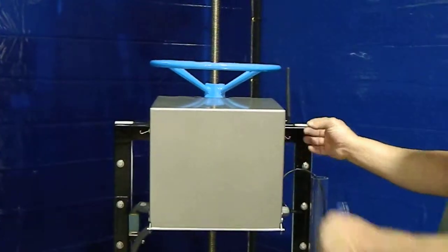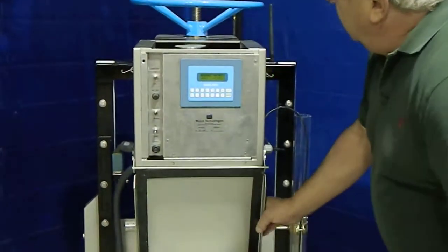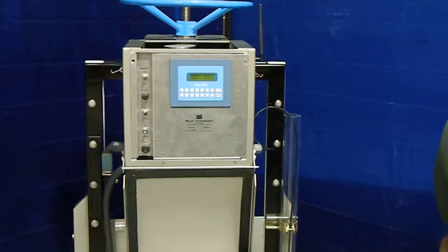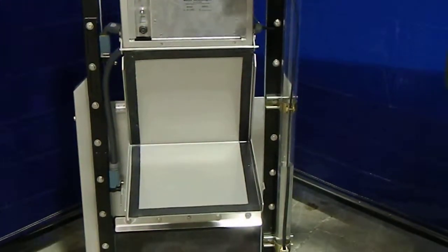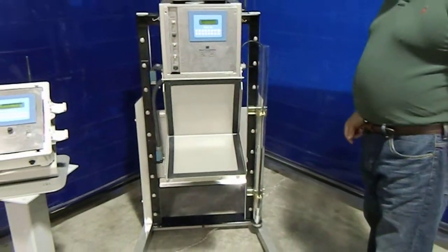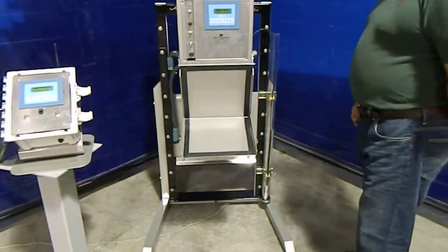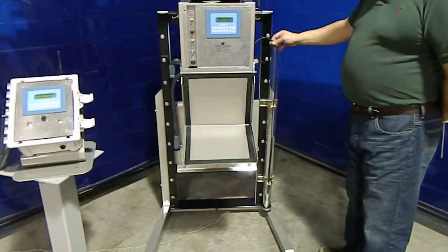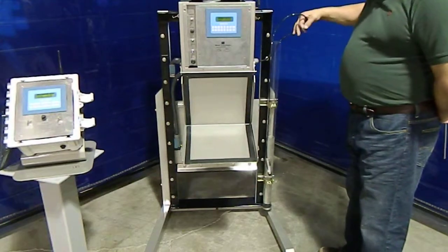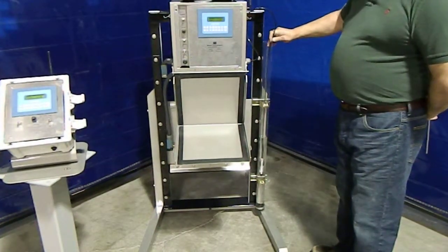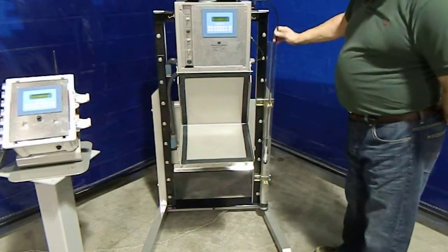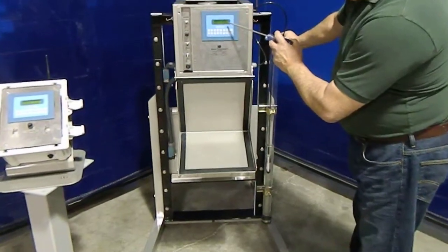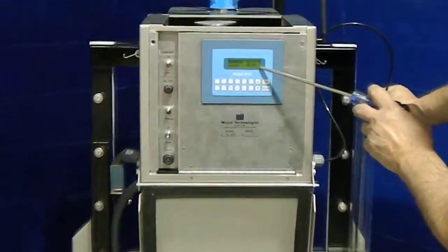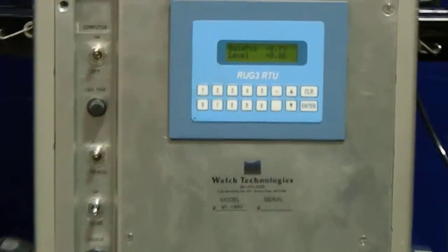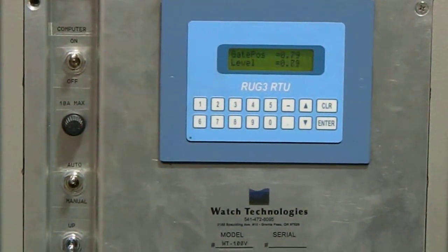The depth thing, you didn't say anything about that. Oh. Actually, we should demonstrate any sensor attached to this system, and these particular RTUs can handle up to 6 analog and 8 digital inputs. But this particular device is a depth transducer designed to measure pressure head, and it's very accurate. You can see now that I'm raising it, and it's lowering the level of water that it's reading over its surface. So we're down, it's probably going to get down to a pretty low number.